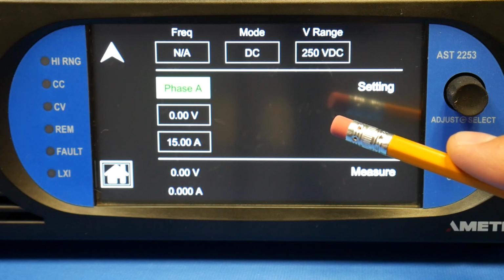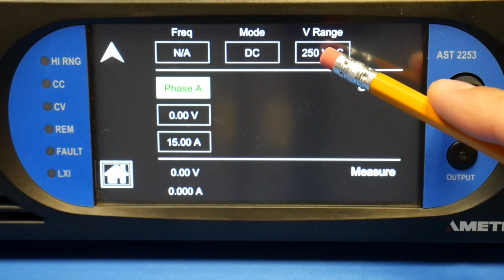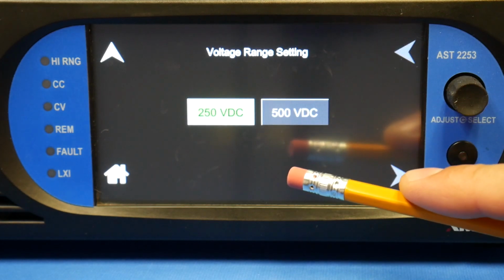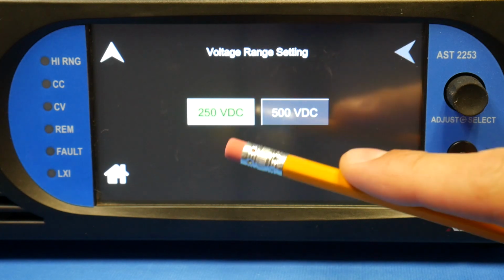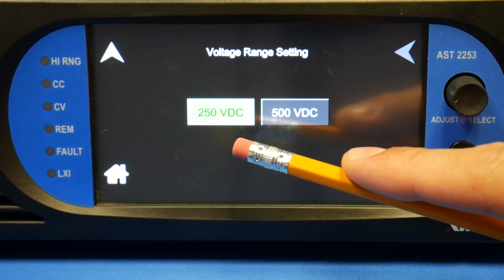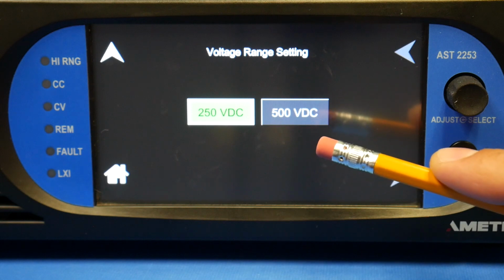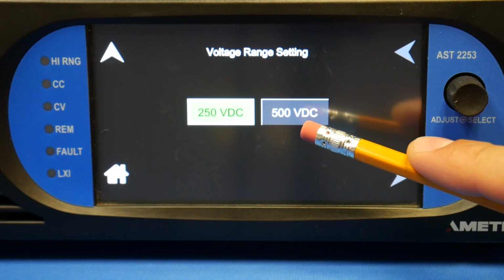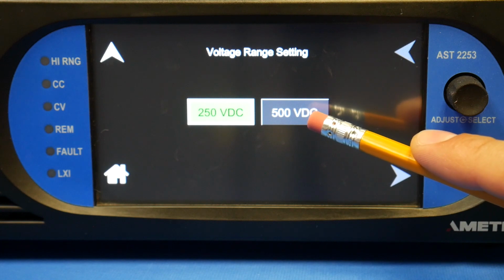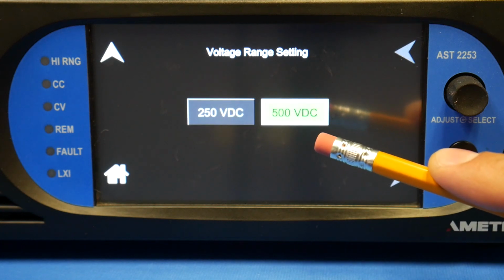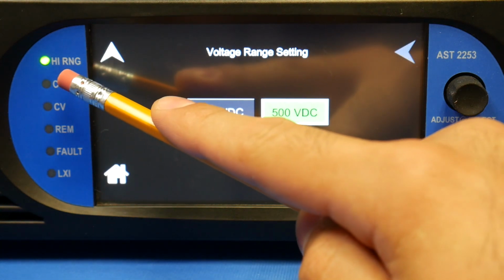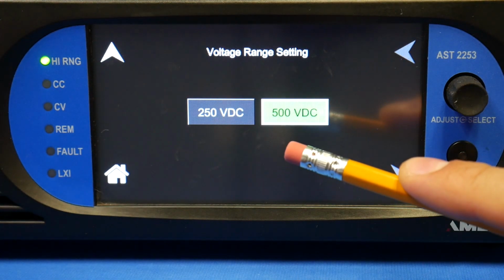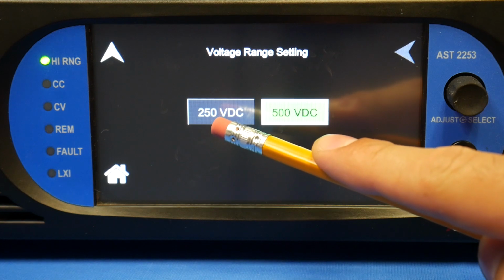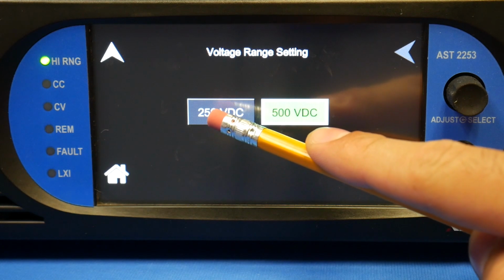Thereafter, we will select our voltage range. The Asterion has the capability of going from a 250 voltage setting up to a 500 voltage range setting. If you select the 500 voltage range setting, the high voltage light will illuminate. Since we're conducting a low voltage test, we will select the 250 voltage range setting.